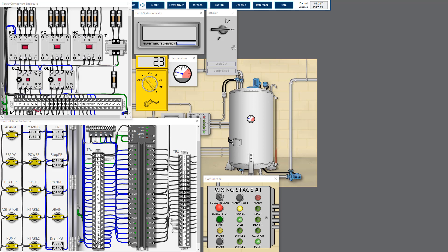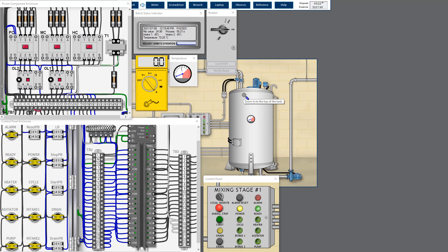So what happened is they pull in a lot of current to generate higher torque to turn the load, but because of the single phasing, the two phases working is not enough to generate high torque. So you're pulling a lot of current, it should finally overheat the overload relay element heating element and trip the overload relay, but it did not do so. The overload relay did not trip initially. So what happened is this will actually cause the overload current to continue to flow through via the overload relay and go to the motor winding and finally cause the motor winding burn.